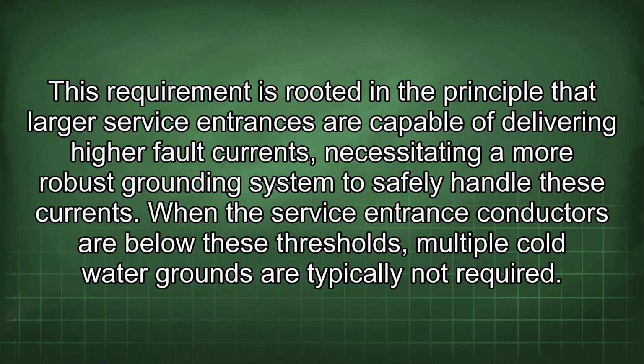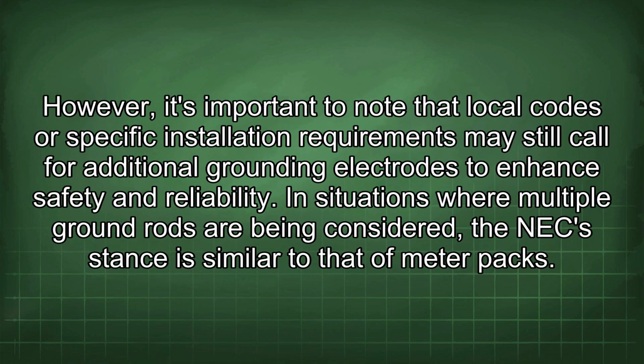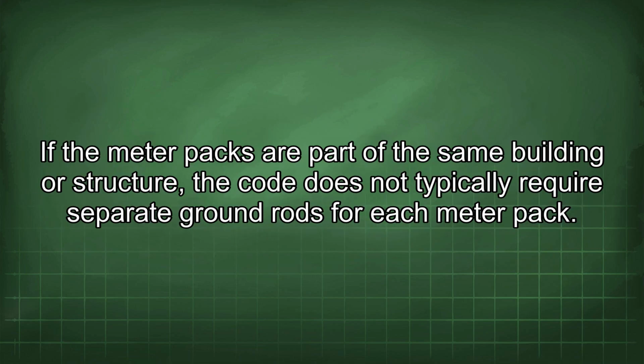When the service entrance conductors are below these thresholds, multiple cold water grounds are typically not required. However, it's important to note that local codes or specific installation requirements may still call for additional grounding electrodes to enhance safety and reliability. In situations where multiple ground rods are being considered, the NEC stance is similar to that of meter packs. If the meter packs are part of the same building or structure, the code does not typically require separate ground rods for each meter pack.